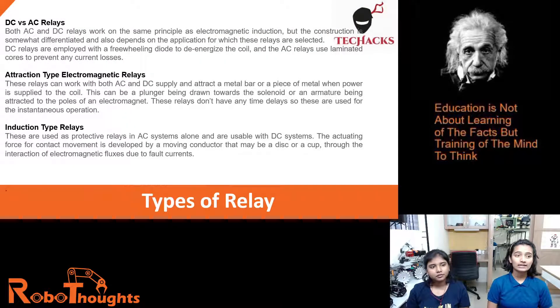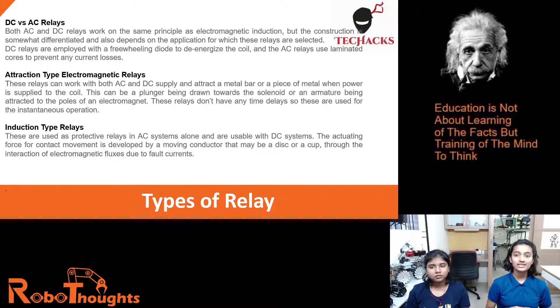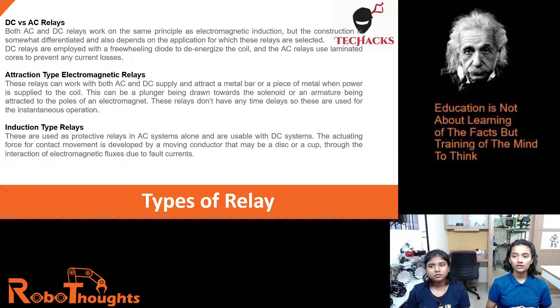The types of relays: DC versus AC relays. Both AC and DC relays work on the same principle of electromagnetic induction, but the construction is somewhat differentiated and also depends on the application. DC relays are employed with a freewheeling diode to de-energize the coil, and AC relays use laminated cores to prevent current losses.